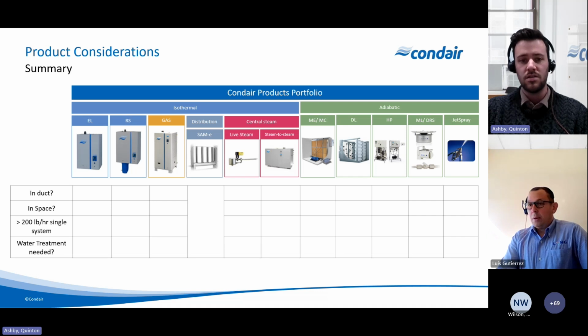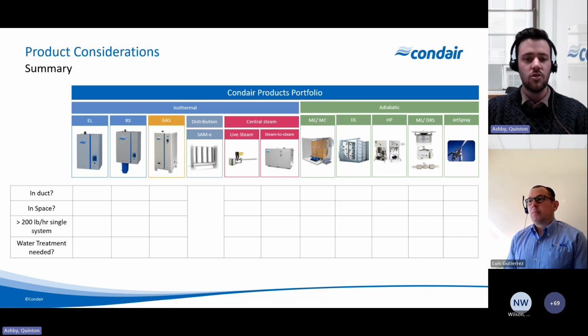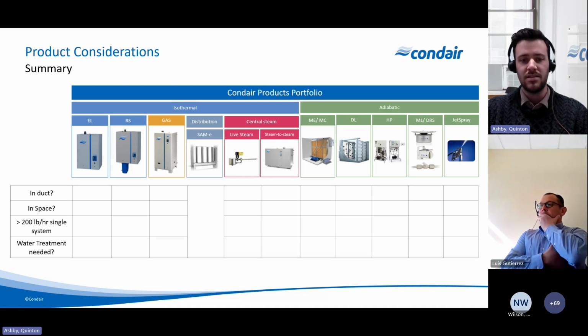The cost savings alone can start to add up very quickly. If you're looking at, say, 1,000 pounds per space, 2,000, it makes no sense to really be using electric humidification in that case. You still can use gas, and you still can use some of the other systems, but they might not be as efficient as an adiabatic, which can actually start to pay off itself. As Nick said, the initial cost is usually a little bit higher on the adiabatic systems compared to the isothermal, but we can do an energy analysis. We can actually look at utility rates and see if it would make sense for your application or not.